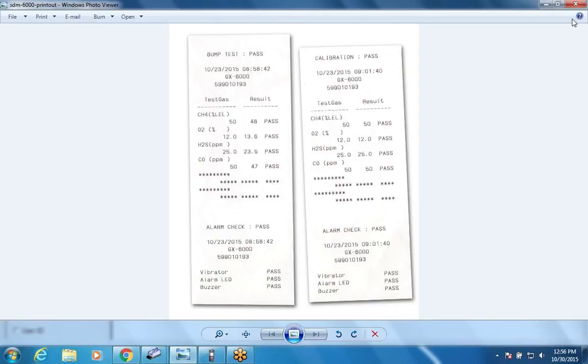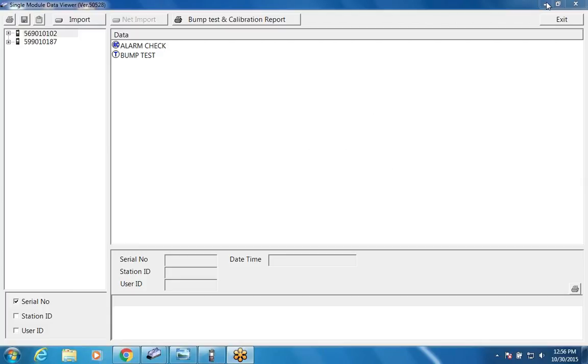I'm not going to get into the software much right now because there are a lot of bugs in it, it's not really very functional. But all three softwares we're going to have for this unit — the data logging software is identical to the data logging software for the 2009, the 2012, and the Eagle 2. The standalone software's only difference from our current standalone software is that you import the data from an SD card rather than a USB drive. You also have the ability, if the unit is connected to Ethernet, to import data from the Ethernet, so you can be on a network and import data from cal stations all over the place. But that's not working yet, so I can't show you that. We're probably going to do another session on the cal station when we're ready to release it and have the software bugs worked out.